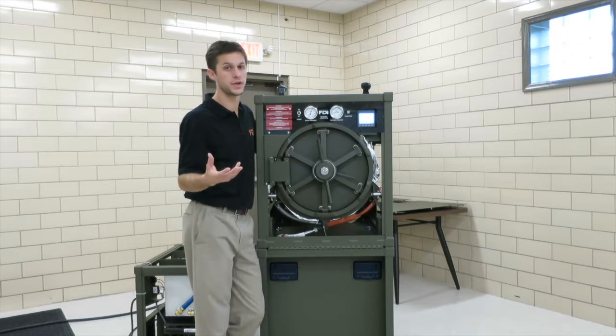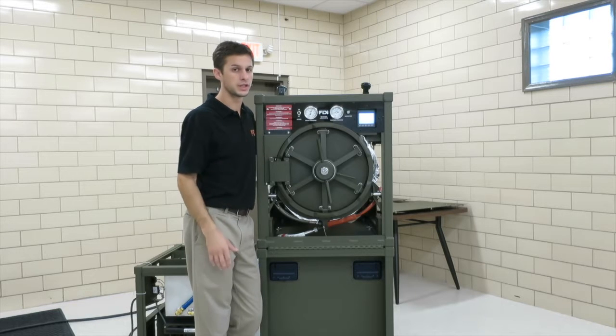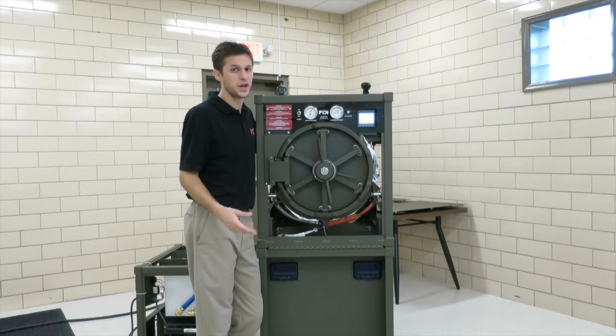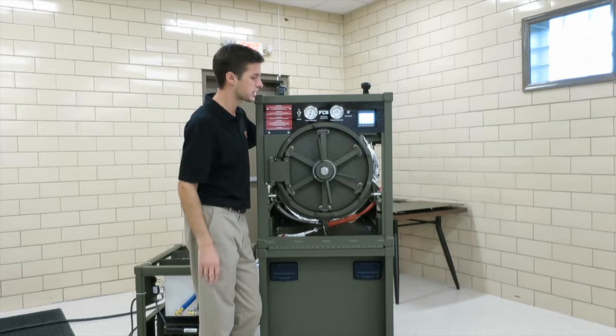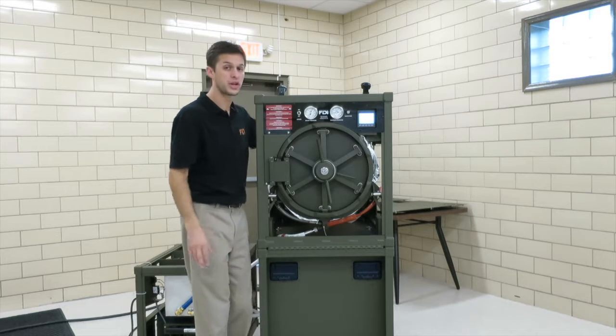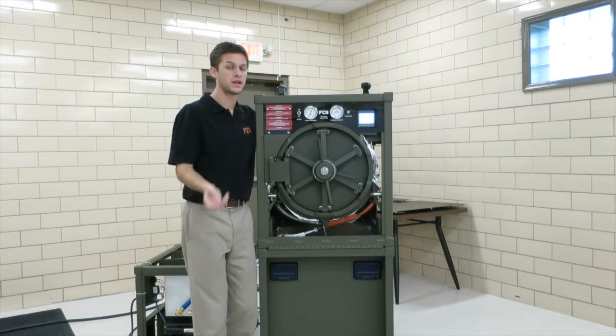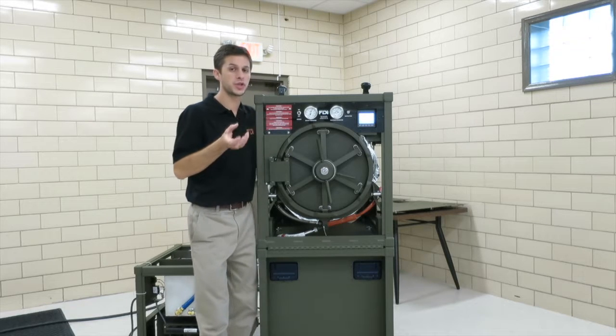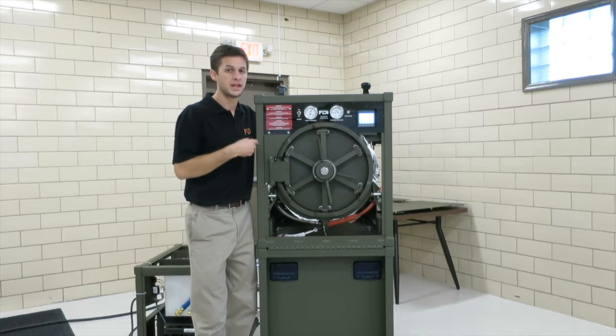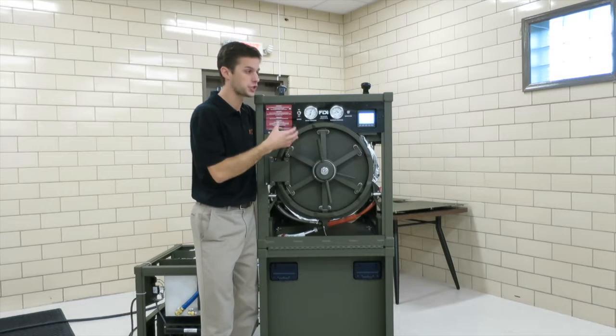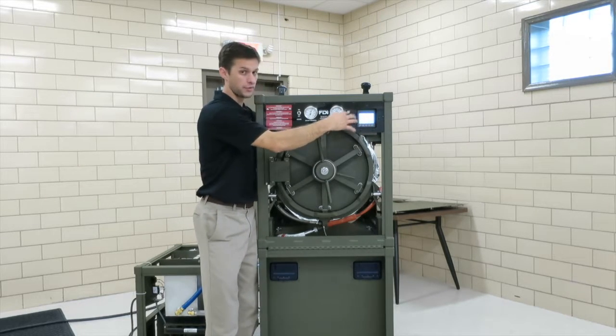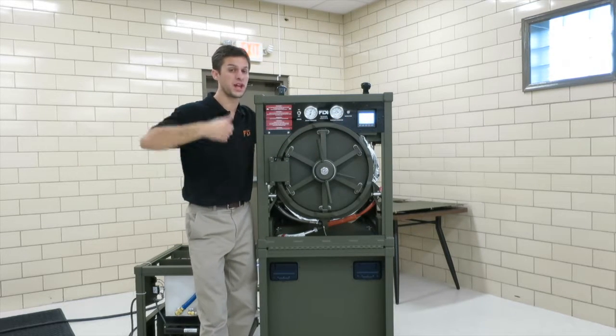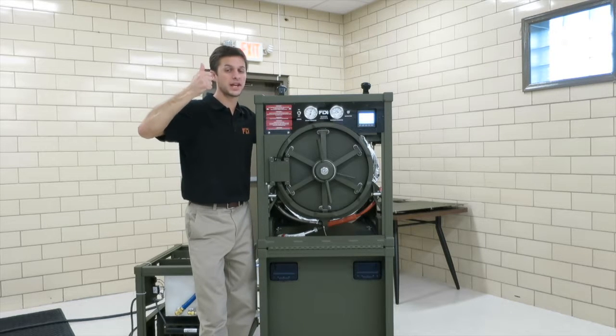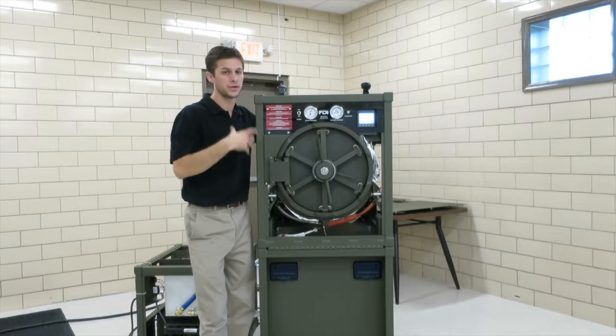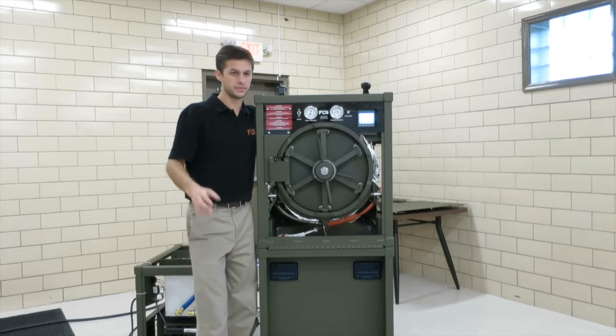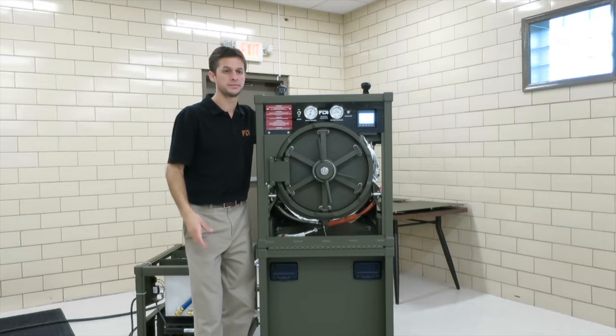So 09 jacket pressure high. Again, the pressure transmitter that's measuring the pressure, it could spike, it could have gotten damaged, causing that alarm. But also, you could have some temperature control issues there. Since temperature and pressure are supposed to be proportional, if, say, the pressure, when it was controlling off of temperature, if they're not proportional, you could have a really high jacket pressure and a lower temperature, so you could potentially get this 09 jacket pressure high.